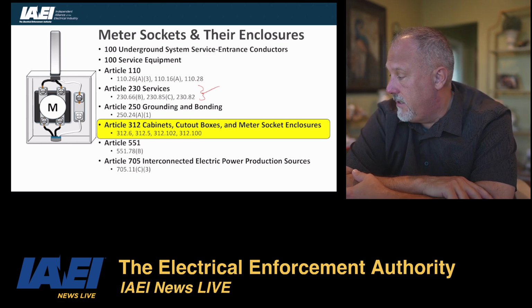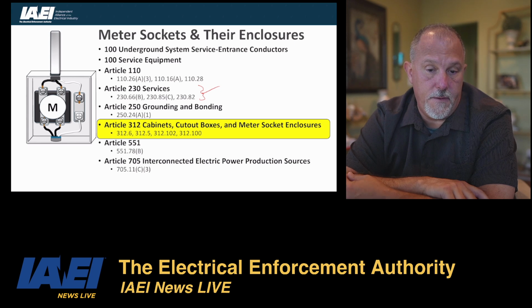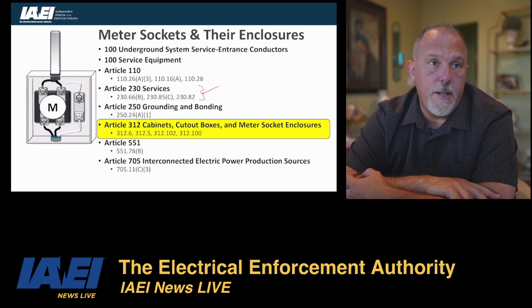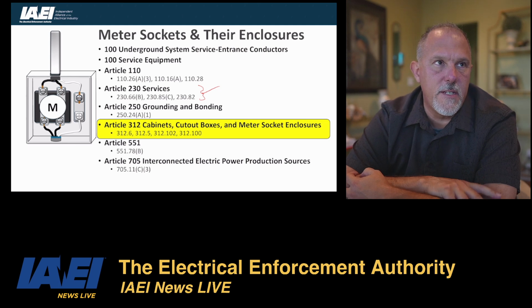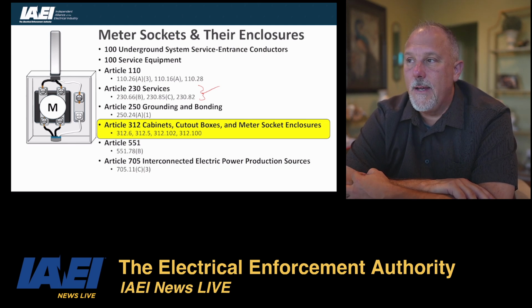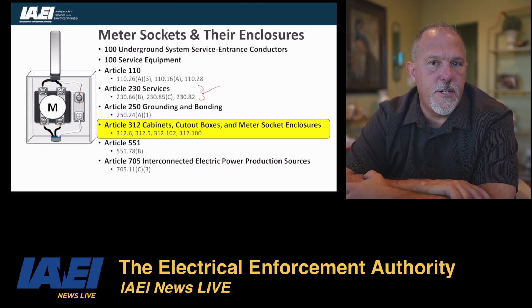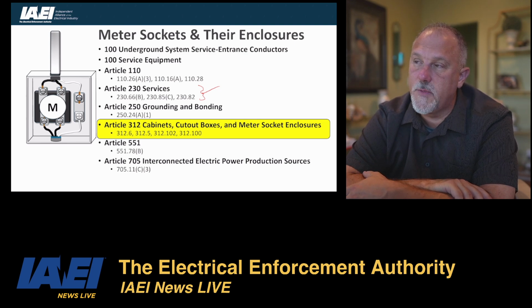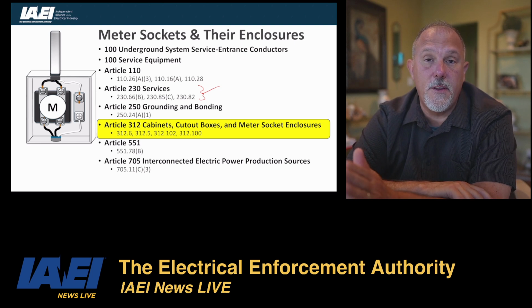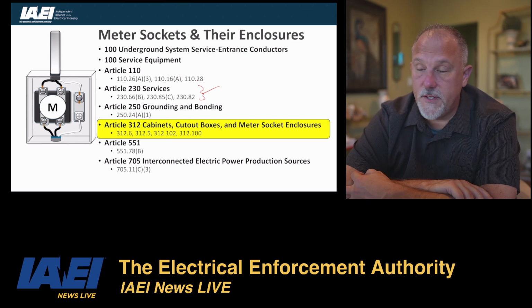Why? Well, I'd make the argument that equipment is probably going to last longer if it's on the inside of the house. I know that the enclosure and everything is listed and rated for the outdoors, but I don't care what the equipment is. You put it in an air-conditioned or a controlled environment, it's going to do a lot better and last a lot longer than if you put it out and expose it to the extremes. Personal opinion on that one, that would be my advice.